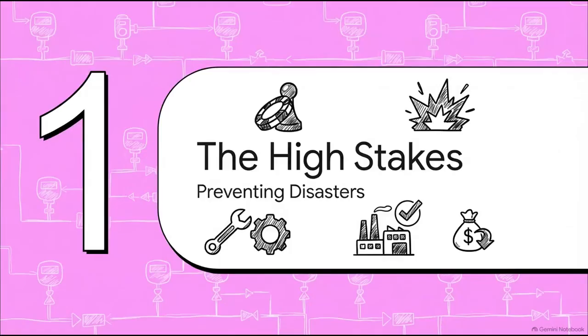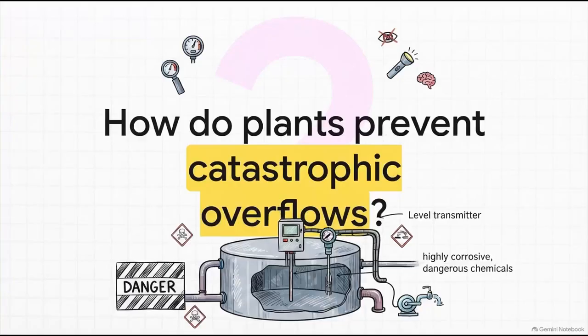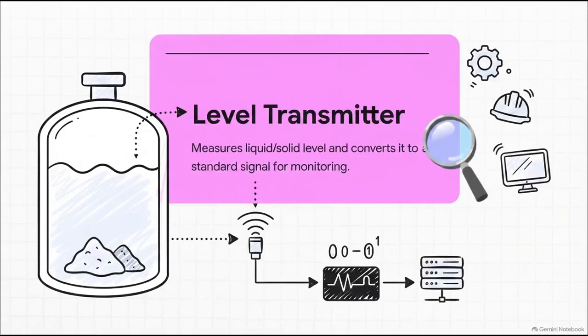Preventing disasters and saving millions. Picture this. You've got a massive storage tank full of highly corrosive, dangerous chemicals. You obviously can't just climb up, pop the lid, and peek inside with a flashlight to see if it's getting full, right? It's way too dangerous. The pressures are extreme, and honestly, human error just isn't an option here. So how do we prevent catastrophic overflows, keep expensive pumps from running dry and destroying themselves, and ultimately avoid massive environmental disasters? Well, the undisputed hero here is the level transmitter.